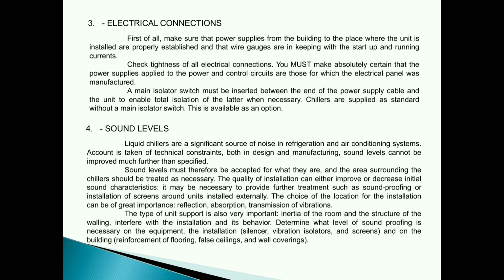A main isolator switch must be inserted between the end of the power supply cable and the unit to enable total isolation of the latter when necessary. Chillers are supplied as standard without a main isolator switch. This is available as an option.